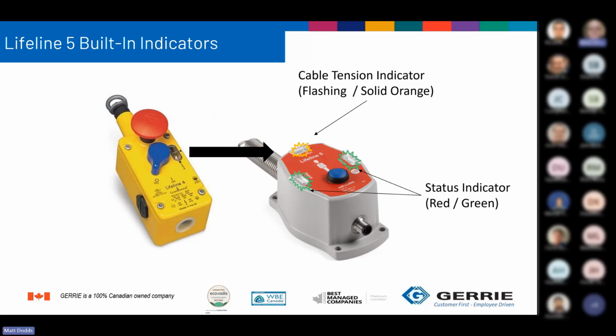So the built-in indicator. I sell a lot of indicators that have to be then put into one of the conduit entrances on the switch and wired in. With the Lifeline 5, it's built in. So there's two sets of indicators. You get the status, which is red or green. So red for tripped or green for operational. And then the tension indicator. So if it's flashing solid, it means I need to tension the cable. As I increase the tension on the cable, the light flashes faster until it goes off, which means, hey, you've got proper tension on the cable. I can then hit the reset button and the switch becomes active.